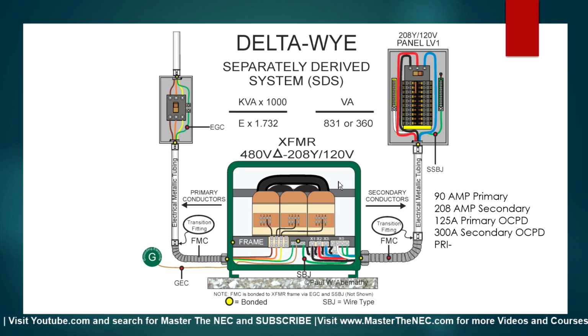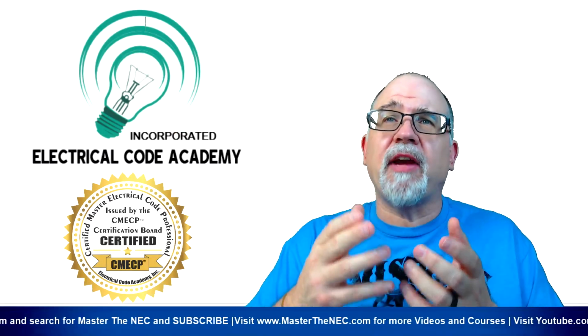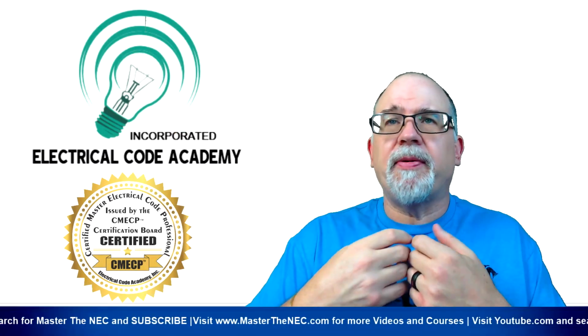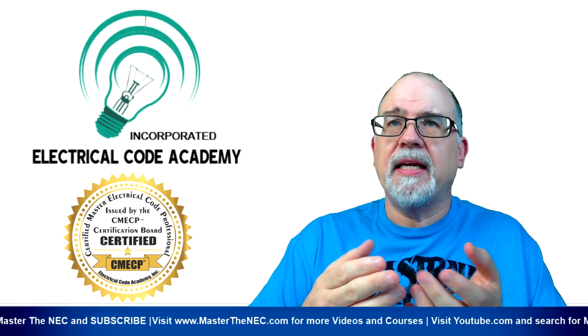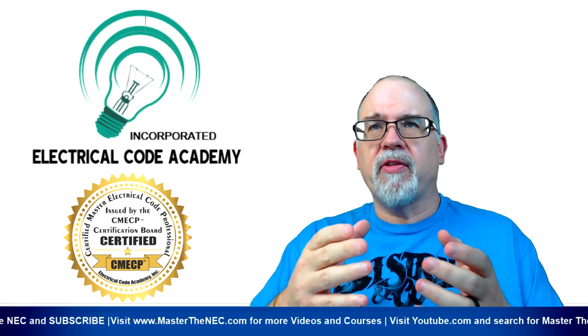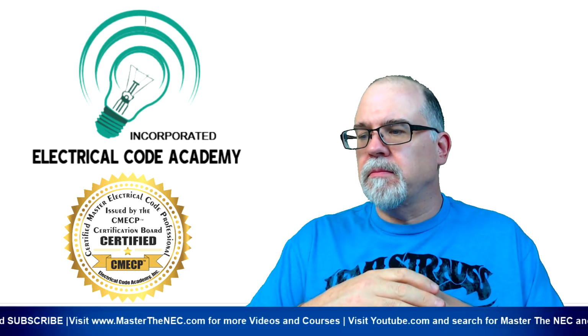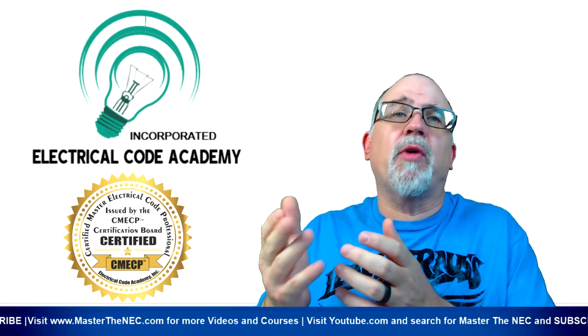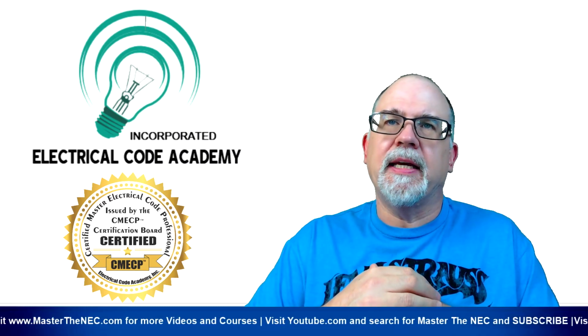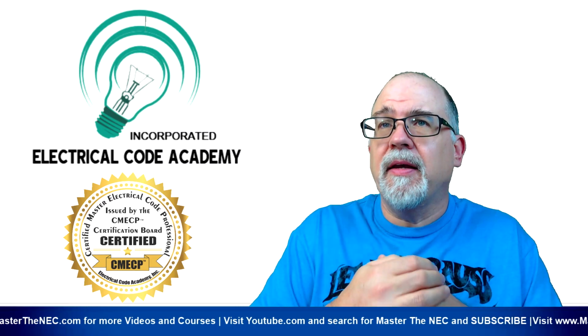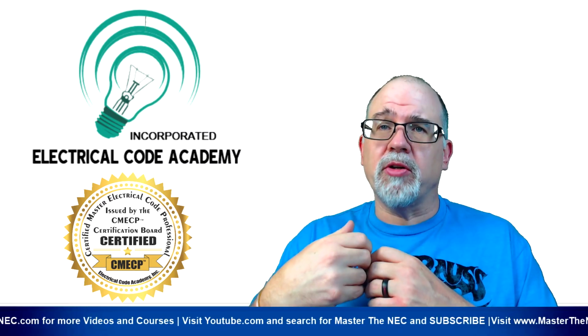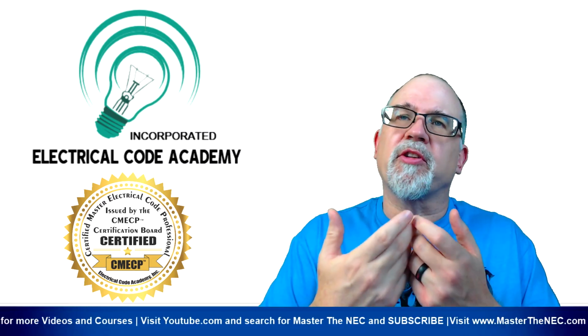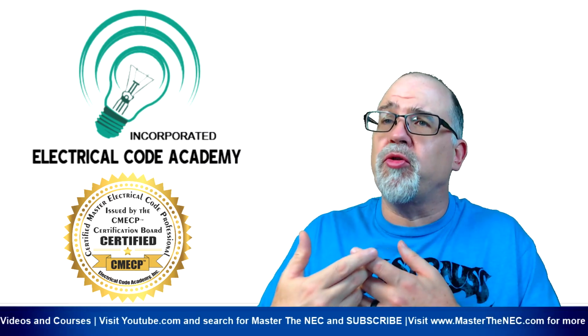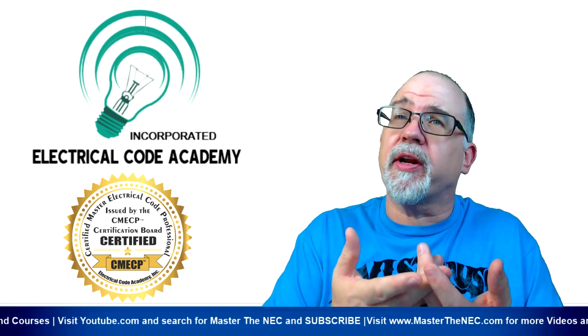Now, let me bring it back and talk about something. I could have a transformer that is only putting out 208 amperes. Could you have a 200 amp panel as a secondary? Absolutely. You don't need to use all the 208. But you have to calculate your load so that it's not going to exceed what the transformer's rating is. A lot of people do that, and they'll overload a transformer and burn it up.